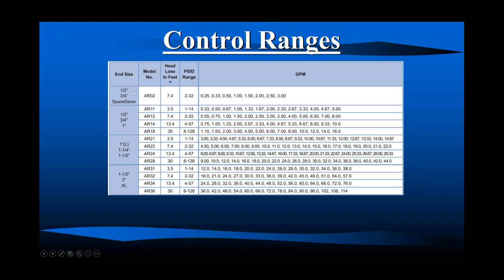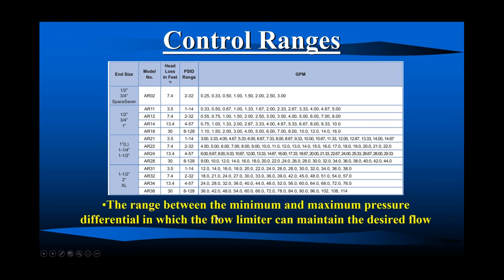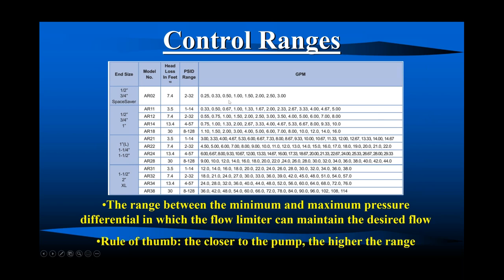So 0.25, again, this is 3/4 inch up to 2 inch there, and you can get a cut for up to 114. Now, it may not get exactly, if you had 2.75, we'd get it cut for 3. The range between the minimum and maximum pressure differential is where the flow limiter can maintain the desired flow or limit the flow. So the closer to the pump, usually the higher the range.